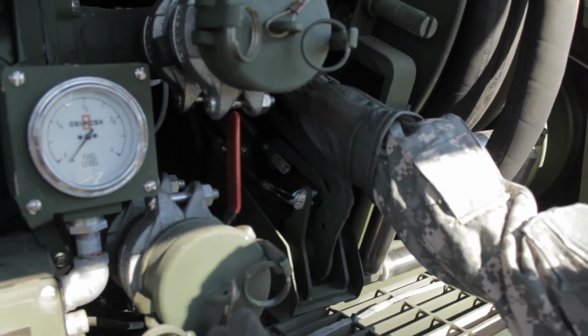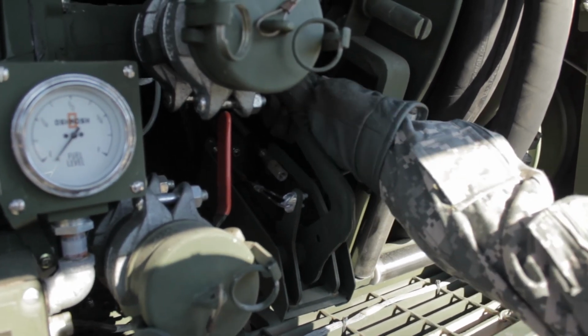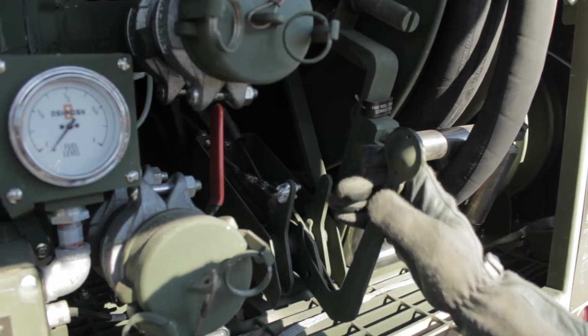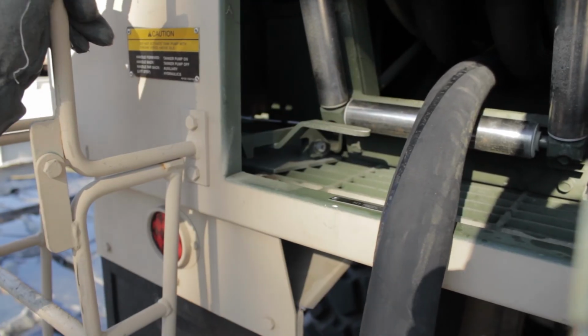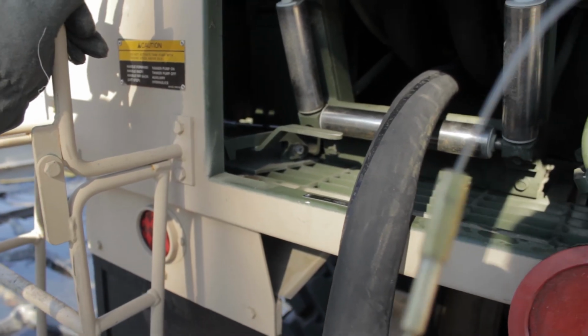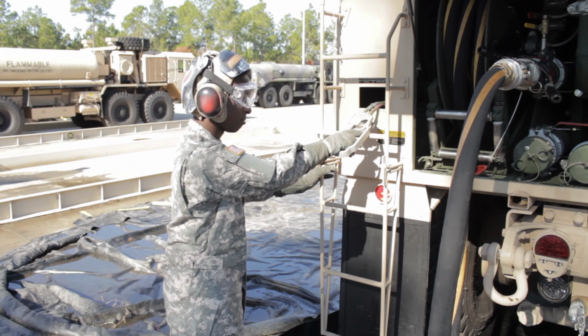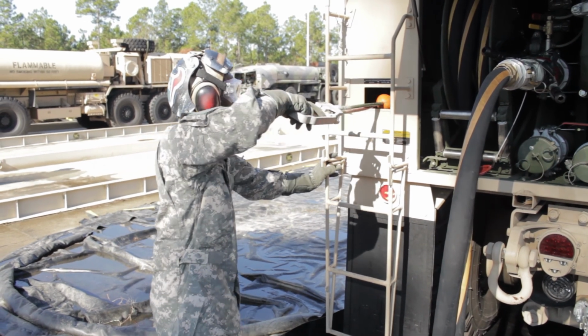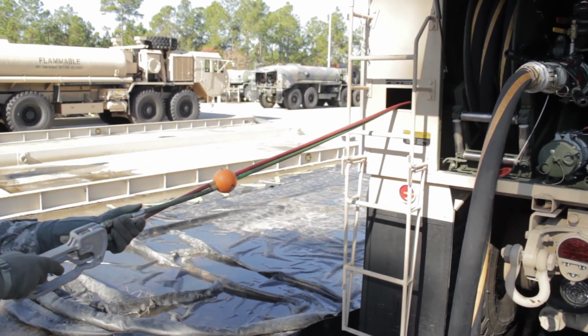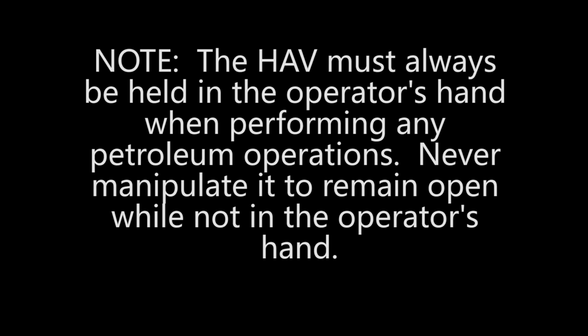Pull out the V1 dump valve to allow fuel to flow out of the tank. Push in the pump engagement lever located on the bottom left portion of the HEMTT pump housing. There should be a distinctive whine which indicates that the pump has been engaged. Pull out the hose to the hand actuated valve and squeeze the HAV to begin the flow of fuel. Note, the HAV must always be held in the operator's hand when performing any petroleum operations. Never manipulate it to remain open while not in the operator's hand.